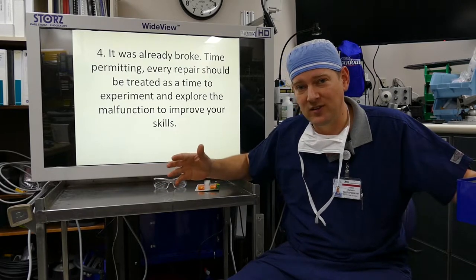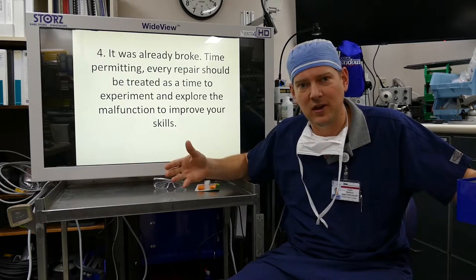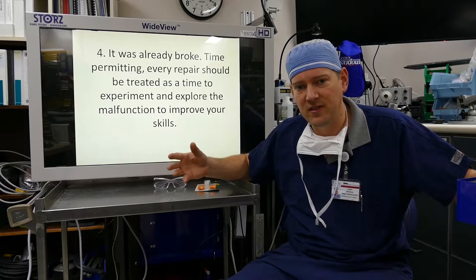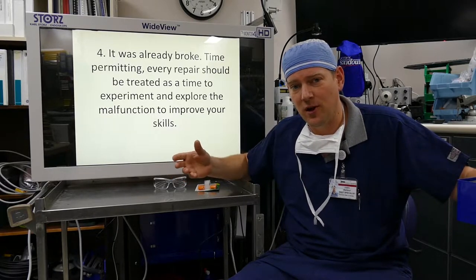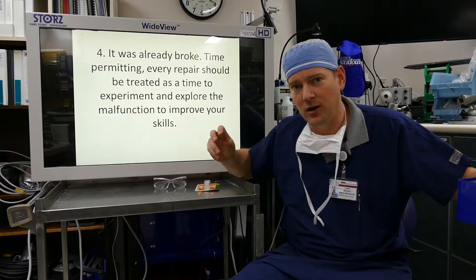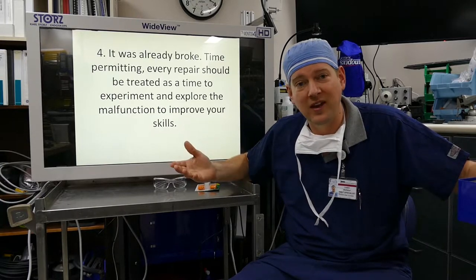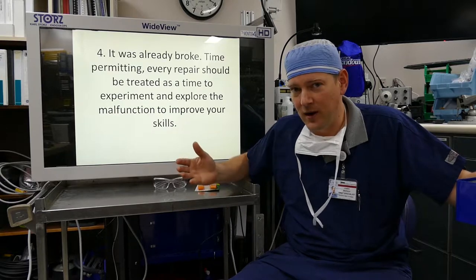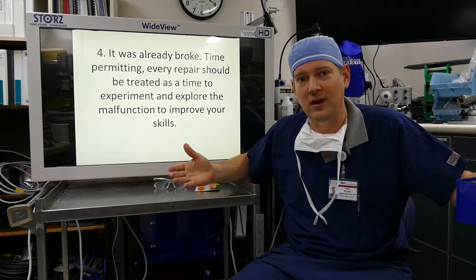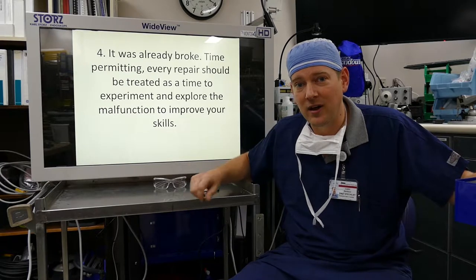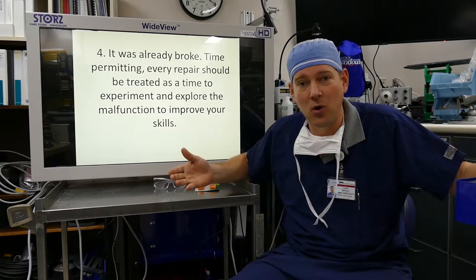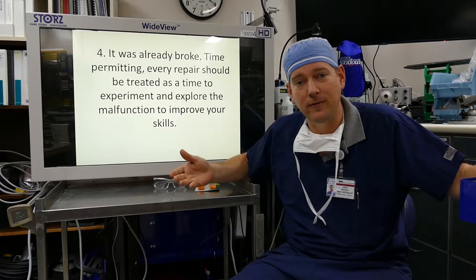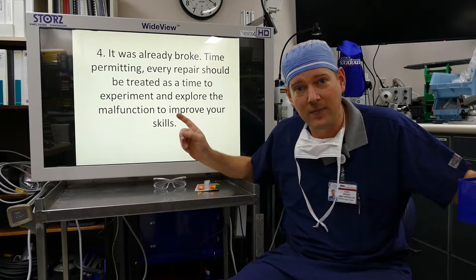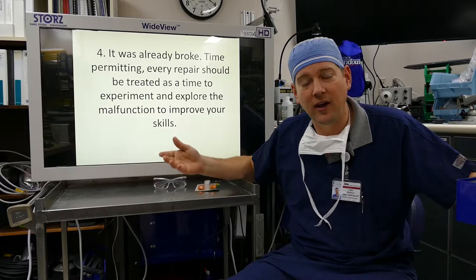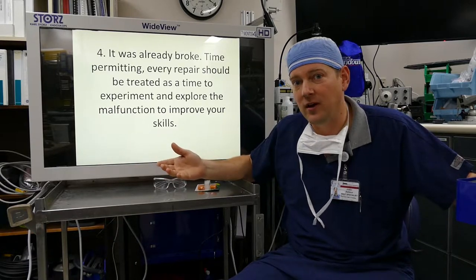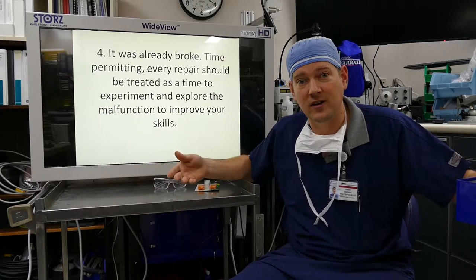We had a camera recently for a CATS machine, which is a cell saver, and the camera was going to cost us $6,000 or $7,000. Since the error was that the CCD showed low sensitivity, why not just open the camera up and check the CCD? Wouldn't you know it, I had a CCD shipped in from Germany and we popped it in. If you have time, it's already broke—you're not going to break it any more. And if you do, well, there's an avenue for repairing that too. If you have the time and you're not under the gun, open it up and explore the nature of the malfunction, so maybe we can head this off on the other units in service.